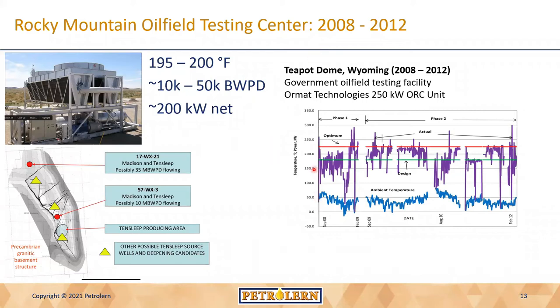One thing I like to point out: the purple line is production, the blue line is ambient temperature. Notice how production increases when ambient temperature decreases - that's because the delta T between the cooling side and the hot water side drives your efficiency. Since these systems are all air-cooled, which is cheaper and often the only option, you'll notice drops in efficiency as you approach summertime, and increases in the wintertime when ambient air temperature is lowest.